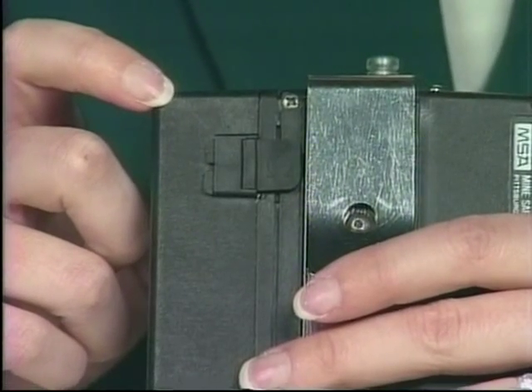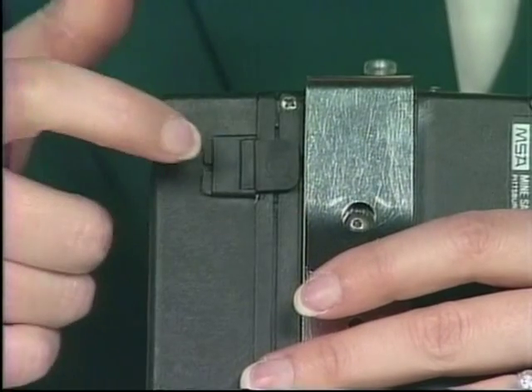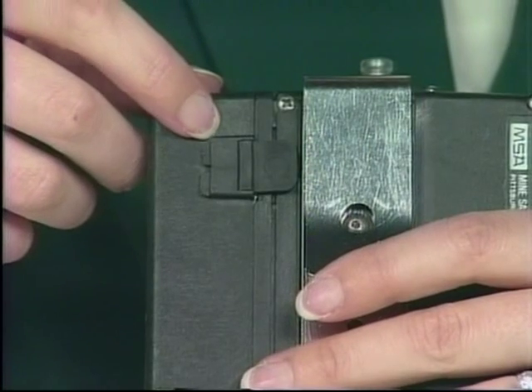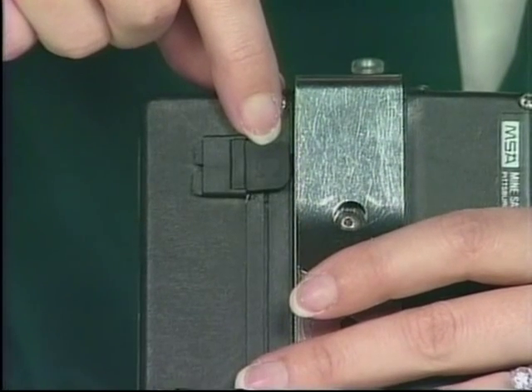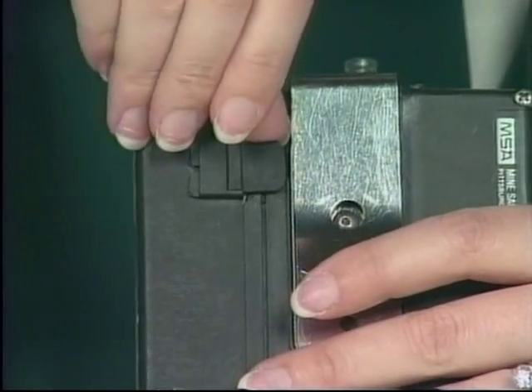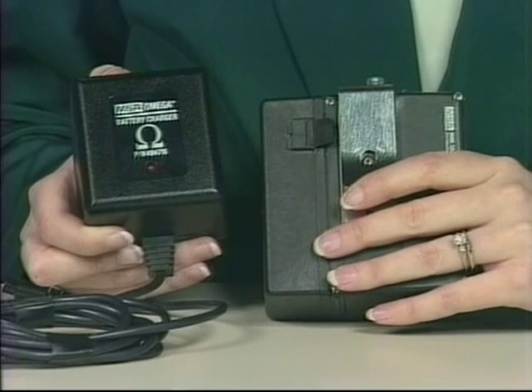New to the Escort Elf pump — and also now new on the Escort pump — is a captive charging jack plug. As you can see, the charging jack plug is captive to the battery pack. This charging jack plug helps keep the pump water tight. There is an Omega symbol on here telling the user they should use an Omega charger. You just pull out the rubber plug and insert the Omega charger into the charging jack.